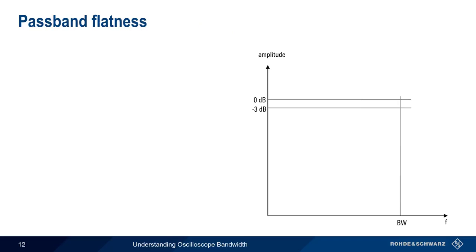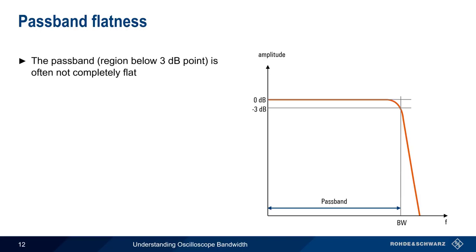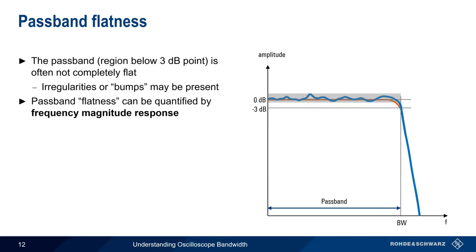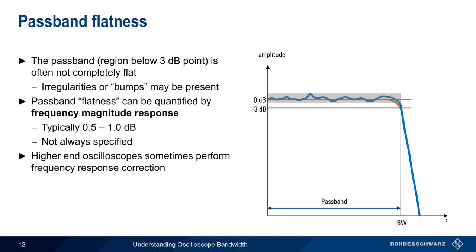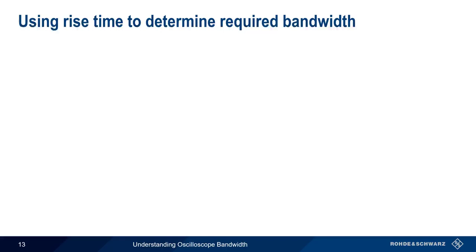One last point about frequency response. We've been showing our frequency response curves as being essentially flat in the pass band, or the region below the 3 dB bandwidth frequency. However, the pass band often is not completely flat, but may have various bumps or irregularities. We can quantify this using a term called magnitude frequency response, which is a measure of how much the actual pass band deviates from an ideally flat pass band. Typical values are about ½ to 1 dB, although these values are not always specified by manufacturers. Some higher end oscilloscopes have a frequency response correction function that uses digital signal processing to smooth out the irregularities in the pass band.